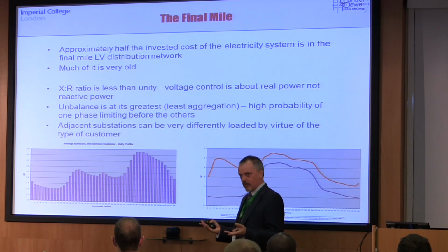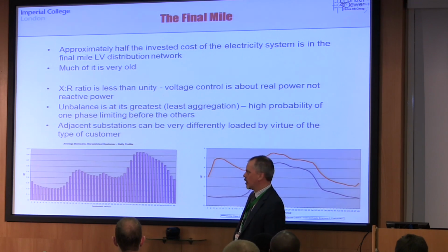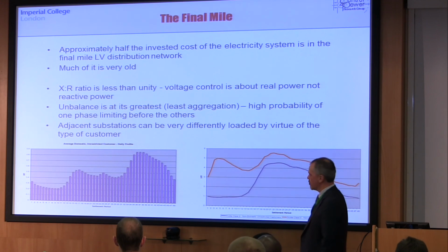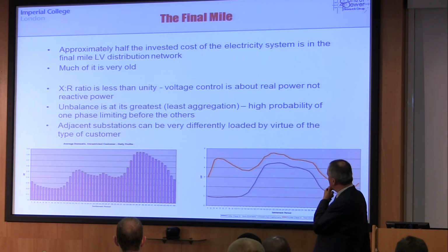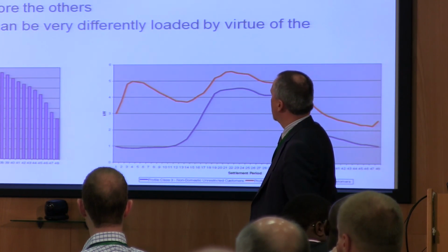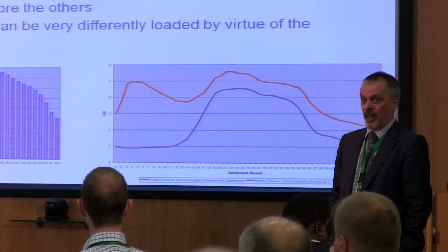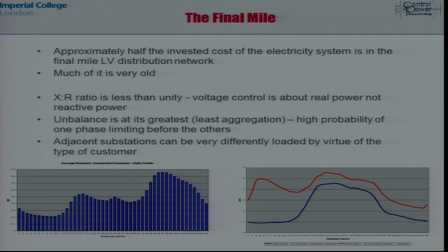So having said a bit about 11 kV, I need to go down to where I was meant to be talking about low voltage feeders. The final mile is what we sometimes refer to it as. So low voltage here meaning 400 volts, three-phase, 230 volts, single. It actually represents probably about half the sunk cost of the network. That cost was sunk, though, probably 50 or 60 years ago. But it would be highly disruptive to replace that infrastructure. And much of it still has lifetime left.